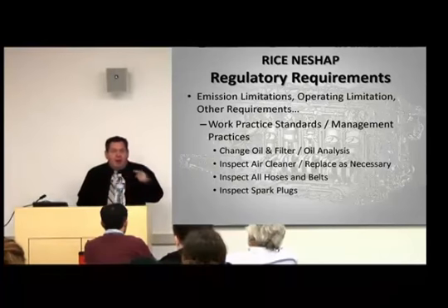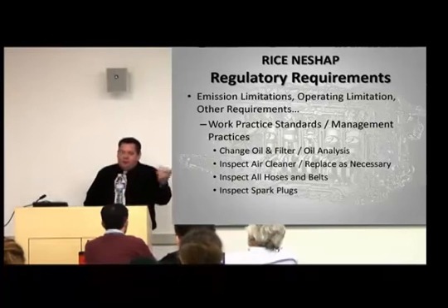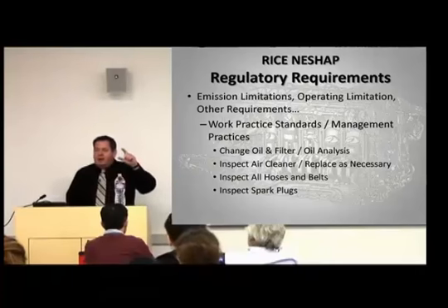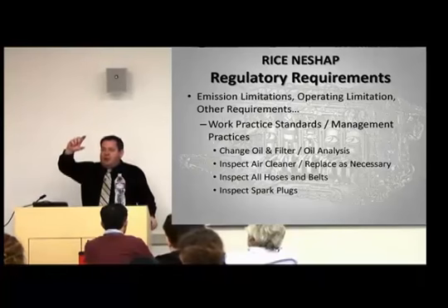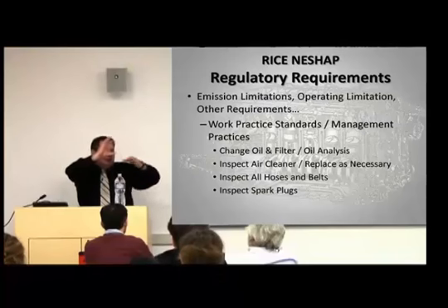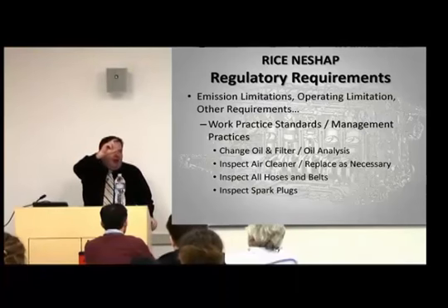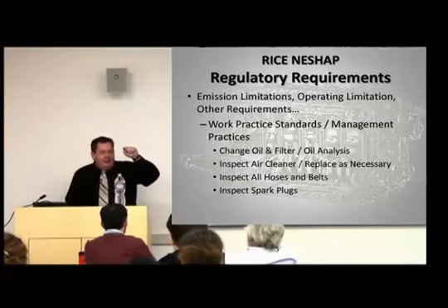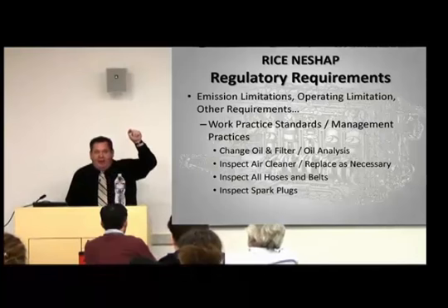Again, high emissions. One thing I would stress to inspectors and even the regulated community is that on your smaller engines, there's going to be a clear plastic bubble, like a little cylinder, on the air cleaner housing. It has minimally a green indicator and a red indicator, and sometimes in between it's yellow.